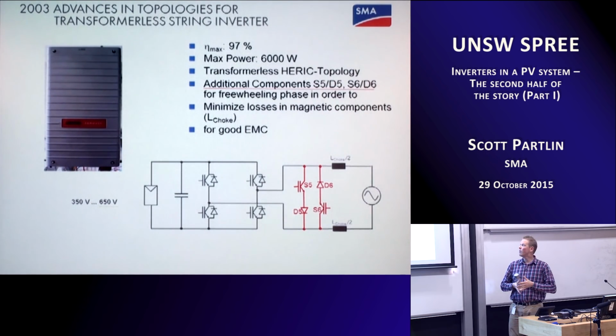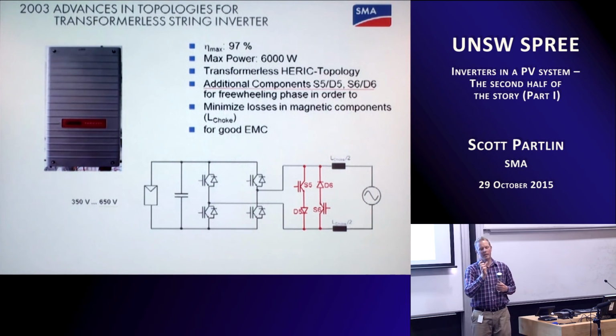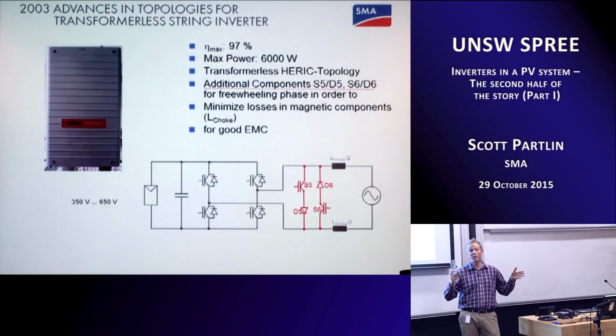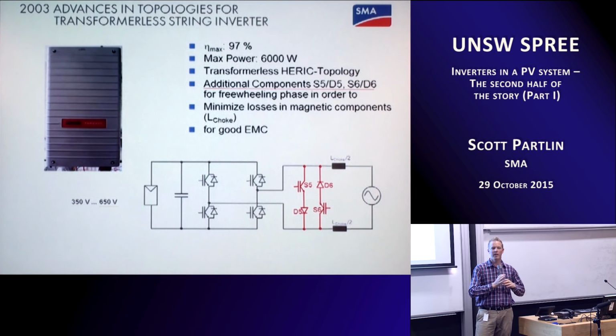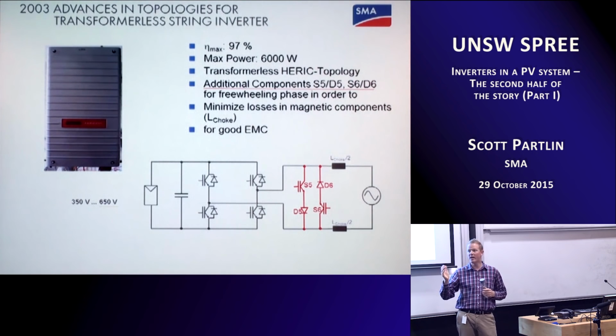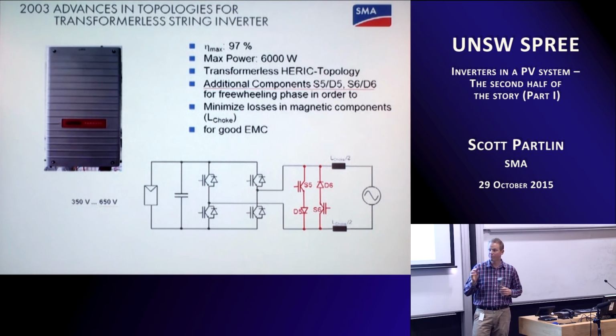One of the problems until that point with a PV inverter was that the DC window with which it was able to operate, with which its maximum power point tracking actually worked, was quite narrow. That meant that in designing a PV system, it could be somewhat restrictive in what sort of PV modules you could use, or how long the strings could be, and there was also a floor meaning they had to be at least a certain number - the window between the minimum and maximum was quite small.